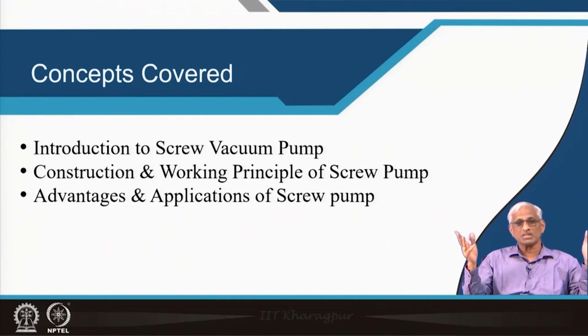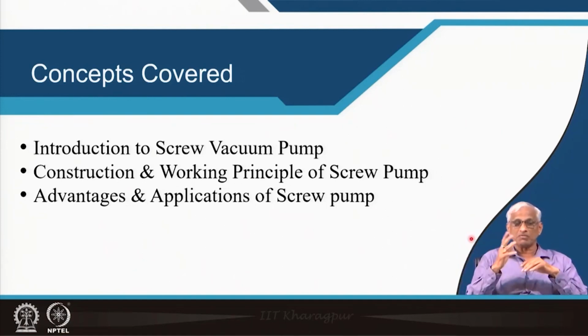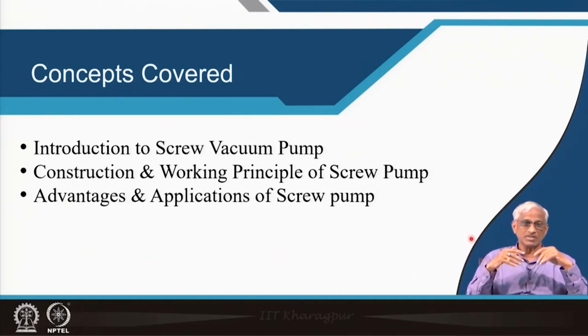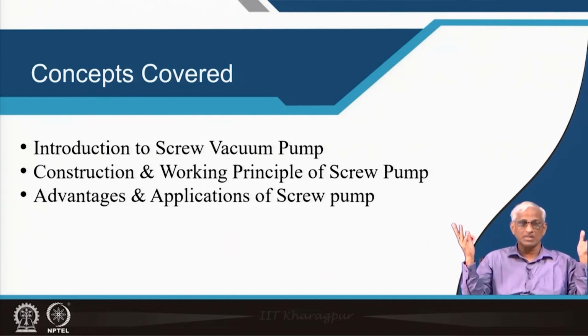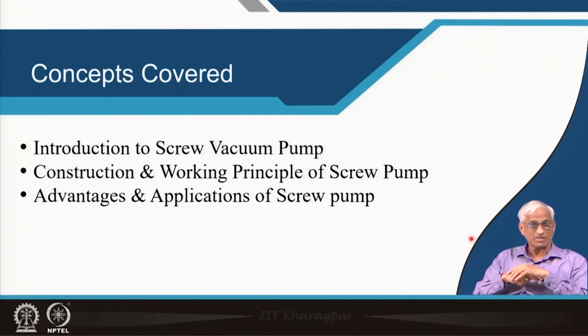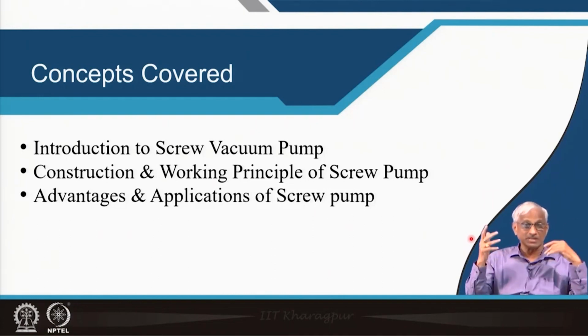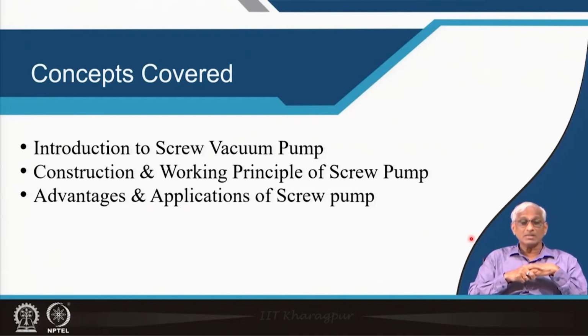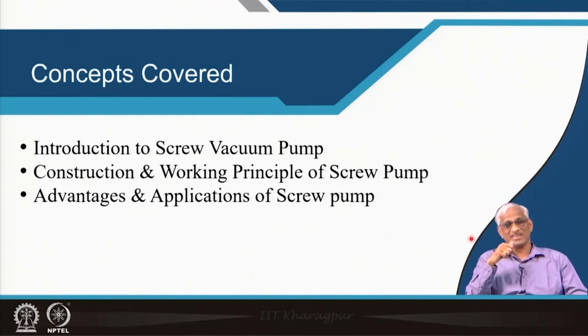The working principles of a typical screw vacuum pump that is being used in several process applications all over the world now, particularly pharma and chemical, but it is also used in other sectors like metallurgy, electronics, electrical, and now people are trying to go into other sectors where hogging of very large chambers, even in space or nuclear technologies, you can use it. Metal degassing, steel, you can use it, because they have got huge pumping speed. Their range is of the order of the rotary pump range, but most important is they are very dry.